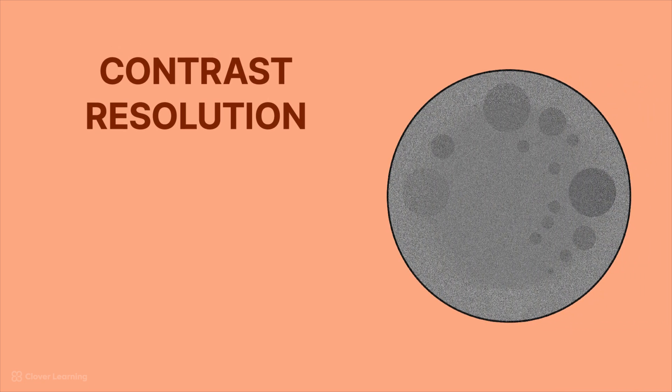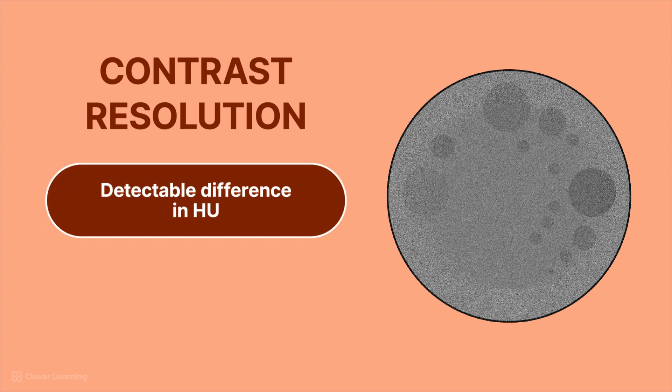Another test that has to be performed on a regular basis is the contrast resolution test. Remember that contrast resolution is the detectable difference in Hounsfield unit. The image that you see on the right is an example of a contrast resolution phantom.